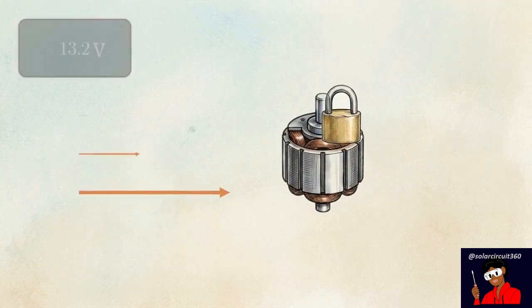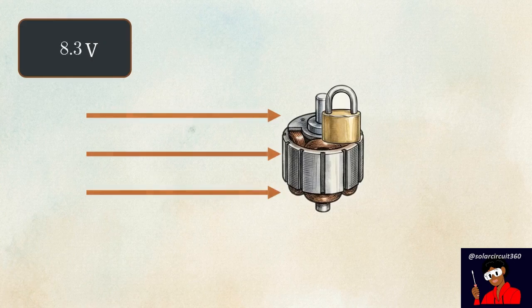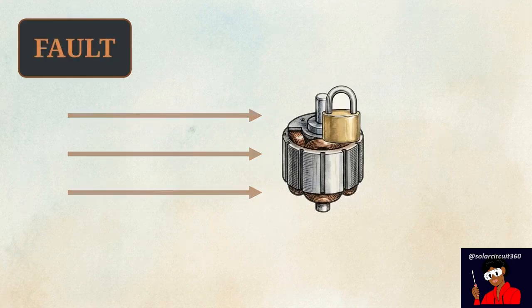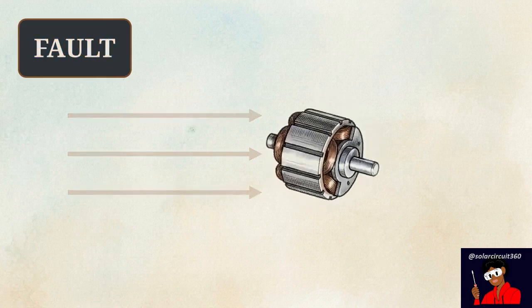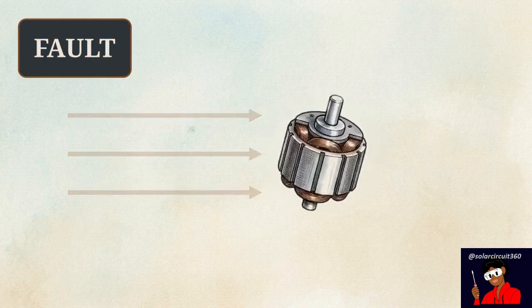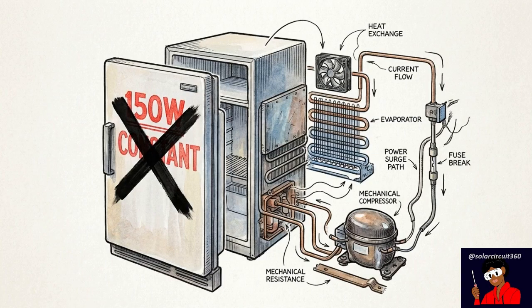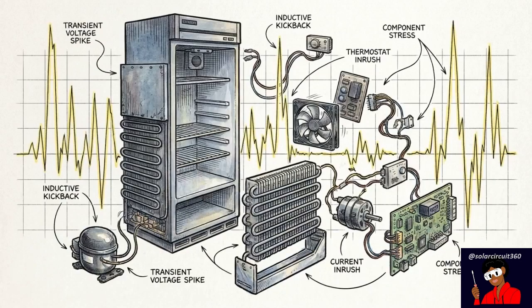The system collapses because it is being overwhelmed by mechanical inertia, specifically the unpredictable, instantaneous electrical energy required to force a heavy physical object to move from a dead stop. To engineer a system that survives, you must stop treating the refrigerator as a fixed-watt device. It is a highly dynamic, transient load system.